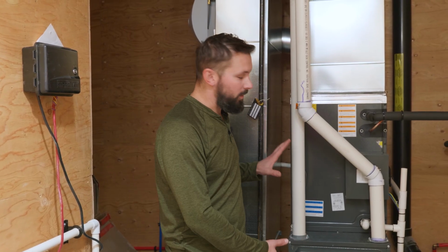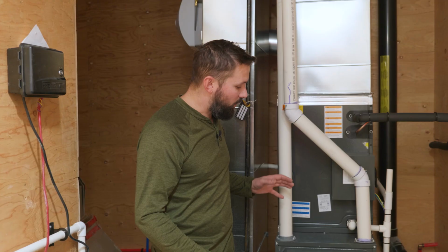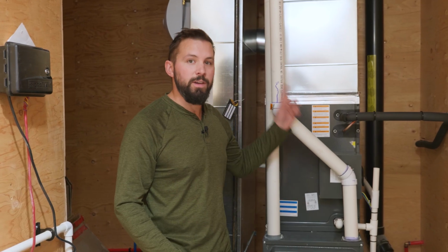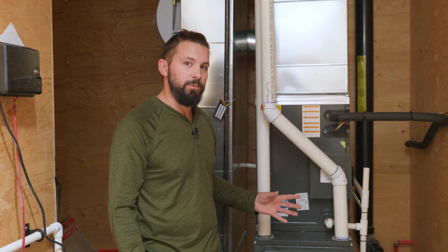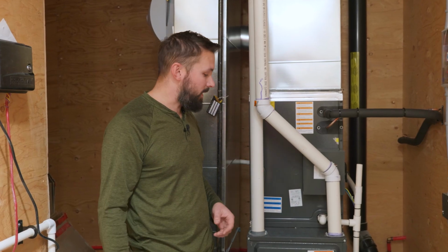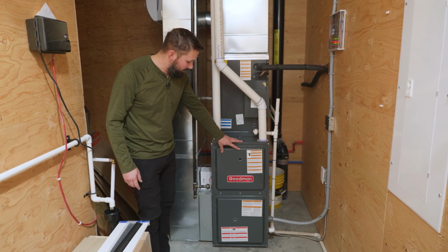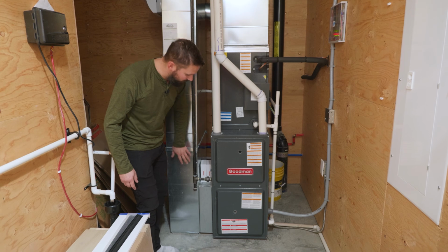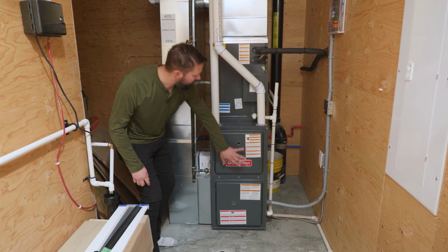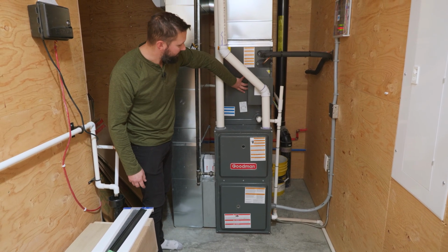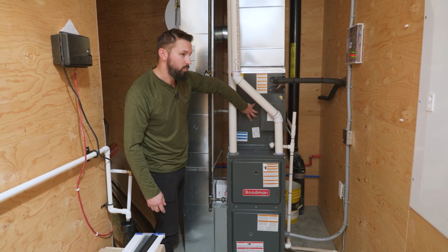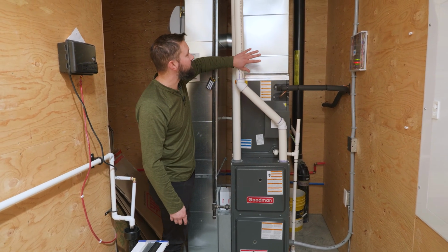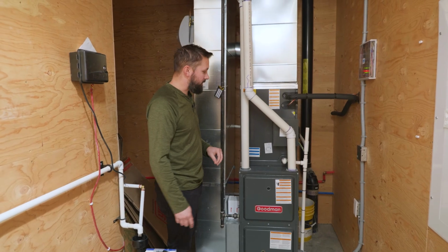Our primary piece of equipment in most homes is going to be a piece of equipment that looks something like this. At its core, it's a big fan that blows air around the building. We have different methods of adding heat or subtracting heat from that air in order to keep the occupants comfortable. This here is a gas furnace. It's pulling air through this return plenum and through this filter and pushing it out the top through this piece of equipment, which is our heat pump coil, which is going to put heat or subtract heat from the air as it passes through, and then it gets delivered through the rest of the house.